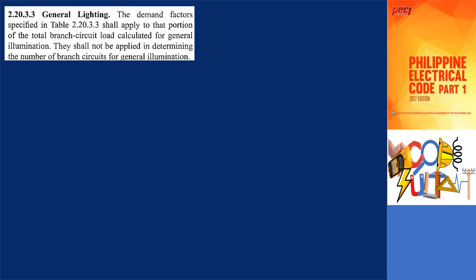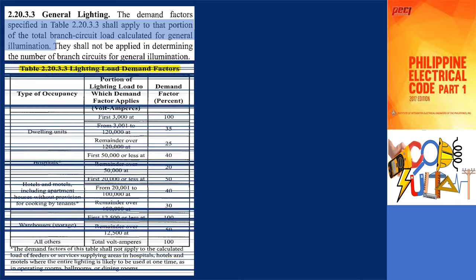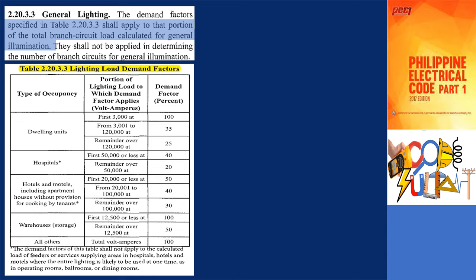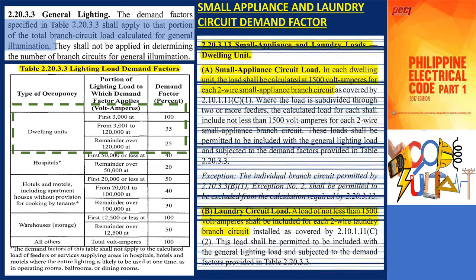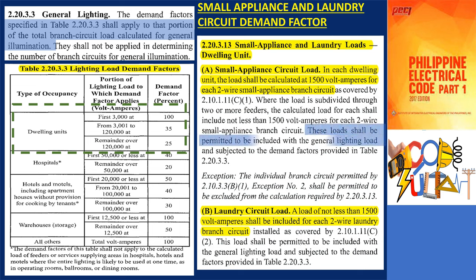Let's start with the general lighting load, as stated in section 2.20.3.3 general lighting, the demand factors specified in table 2.20.3.3 shall apply to that portion of the total branch circuit load calculated for general illumination. For dwelling units, we take the first 3,000 volt amperes at 100%, the range of 3,001 to 120,000 volt amperes at 35% demand factor, and the remainder at 25%. The small appliance and laundry circuits demand factor in sections 2.20.3.13(a) and (b) specifies that these loads shall be permitted to be included with the general lighting load and subjected to the demand factors in table 2.20.3.3.